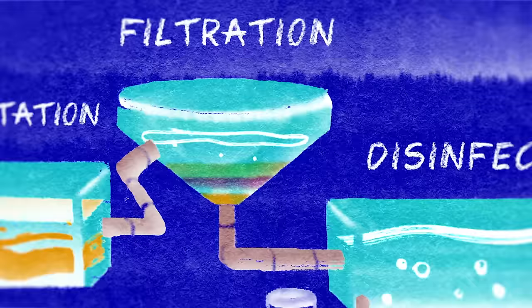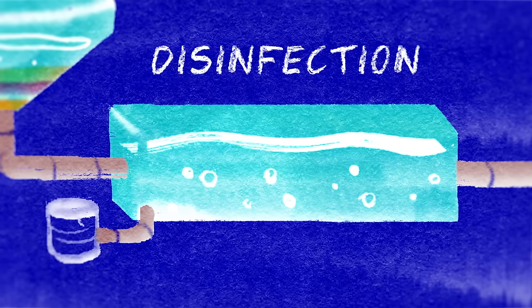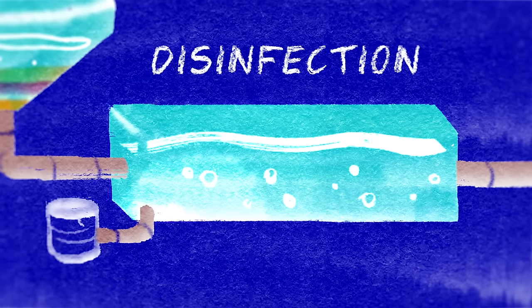Chemicals, primarily forms of chlorine and ozone, are mixed in to kill off any pathogens and to disinfect pipes and storage systems. Chlorine is highly effective in destroying water's living organisms, but its use remains government-regulated because it has potentially harmful chemical byproducts. And if an imbalance of chlorine occurs during the disinfection process, it can trigger other chemical reactions. For example, levels of chlorine byproducts like trihalomethanes could skyrocket, leading to pipe corrosion and the release of iron, copper, and lead into drinking water.